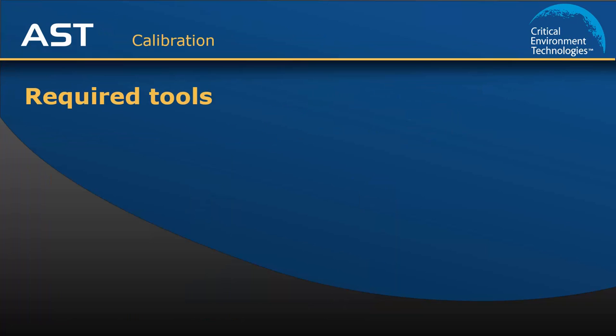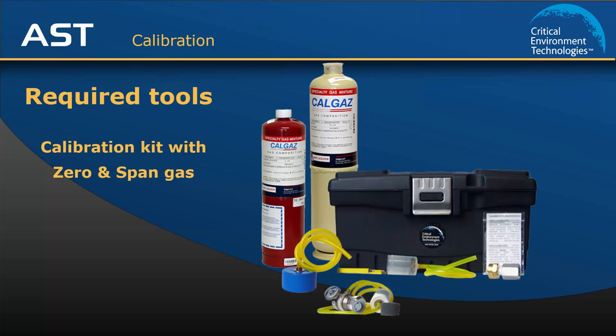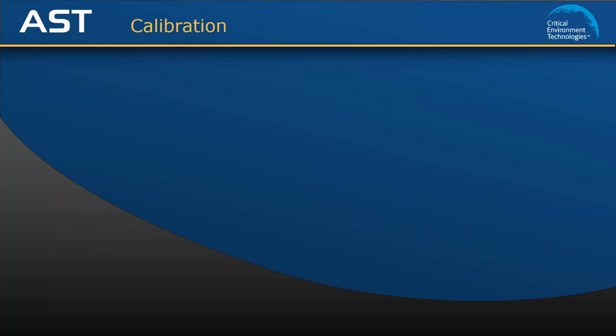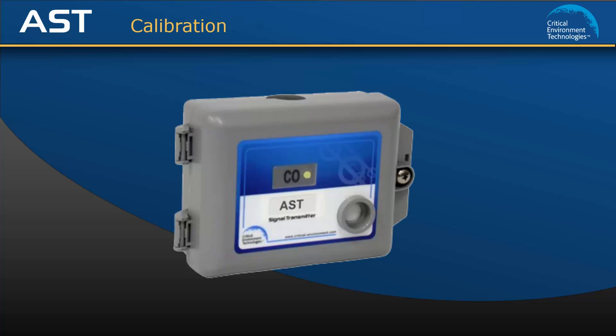To calibrate the AST you will need a calibration kit, gas cylinders with a sufficient amount of the correct concentration and type of gas, and a voltmeter with hook-on leads. It is also important that you make sure the sensor you are calibrating has not passed its life expectancy. In this demonstration I am using an AST with an electrochemical CO sensor.